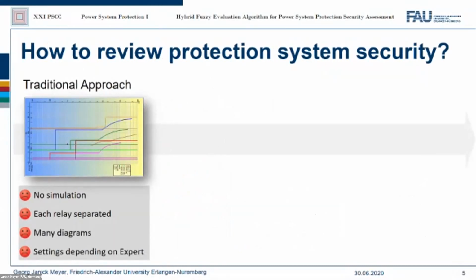The traditional approach is that protection system experts are using various grading charts of protection relays to coordinate everything. However, this method has various disadvantages. First of all, the graphical depictions used are incomplete from an overall system perspective. Diagrams are for one network state and do not support the detection of cascading faults. Without an automated solution, it is impossible to perform systematic protection system reviews on a regular basis.